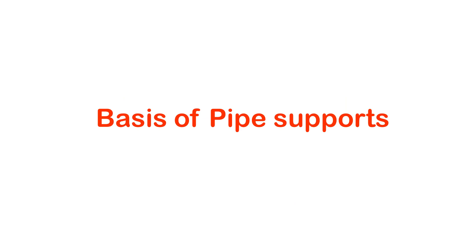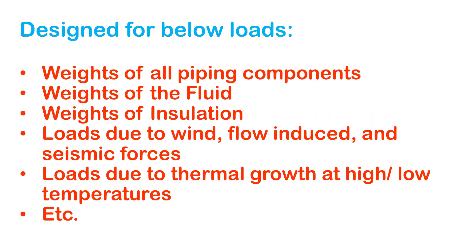Every item in the piping system is designed with a certain basis. Pipe supports are designed to handle certain loads and forces. One of the major loads is the weight of the whole system, which includes the weight of all piping components, fluids, and insulations, and loads such as wind loads, flow-inducing loads, seismic forces, and loads due to thermal growth. There are various other loads and forces upon which piping supports are designed in order to safeguard the whole piping system.